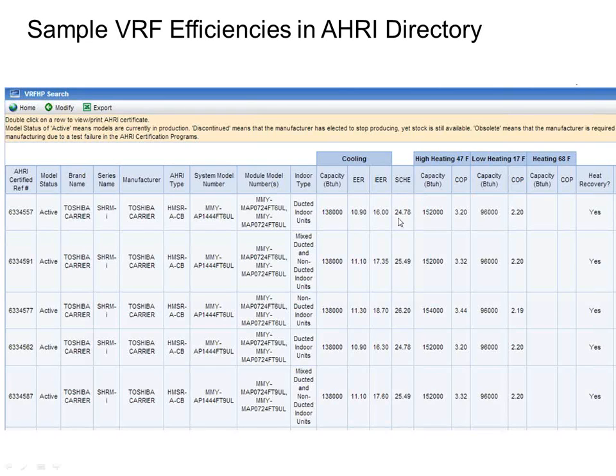One of the things that you'll note, if we look at any one of the energy values you want, EER, IEER, SCHE, whatever, you'll notice that the ducted units are always going to be less efficient than the non-ducted units. I'll circle those right now. So here's some ducted unit efficiencies. Here's some non-ducted unit efficiencies. And you can see the non-ducted ones, the efficiency always goes up. The reason is that I have a lot less fan energy because I don't have to overcome the static resistance of ductwork. And it's easier for me to pump refrigerant a little bit further into the zone than pump it into some central air handler and then duct it over. Like we said before, ducting is the least efficient way to move heat around. So the less ducting I have, the more efficient I get.